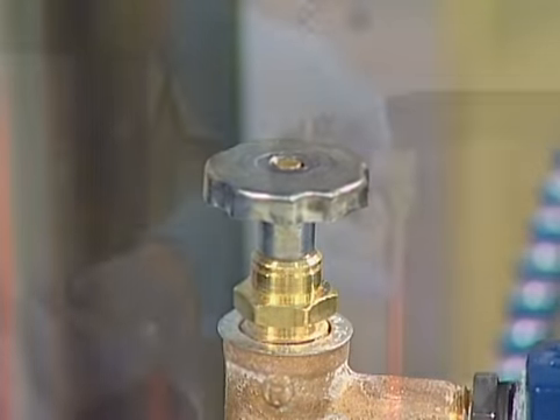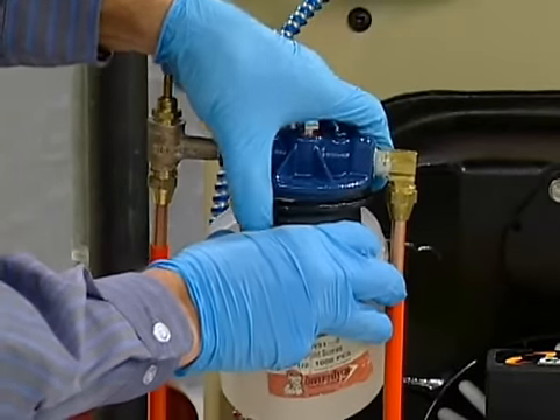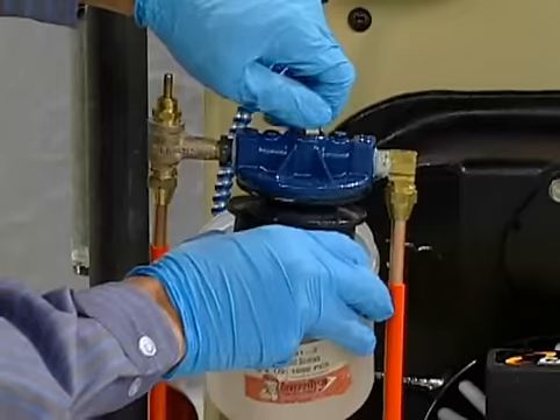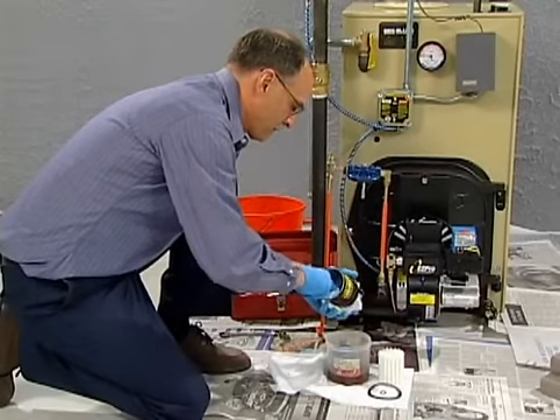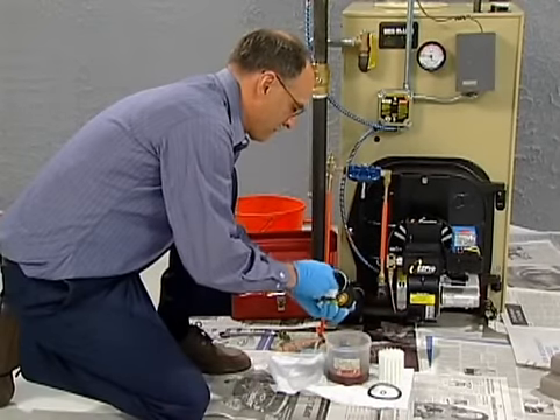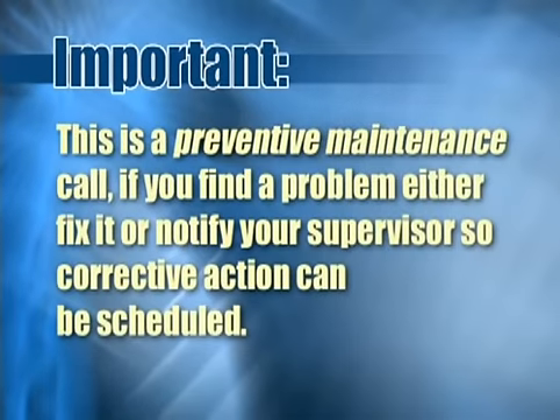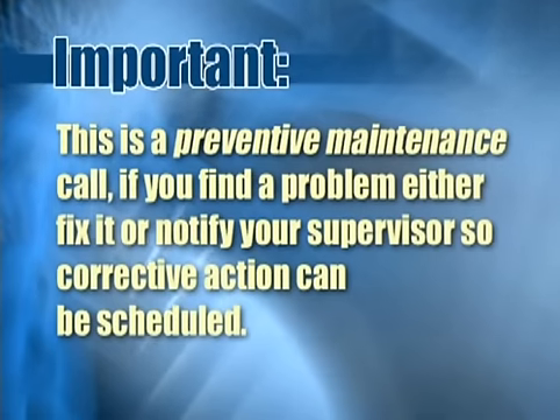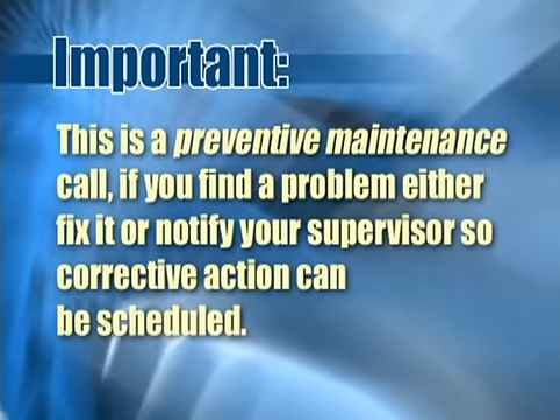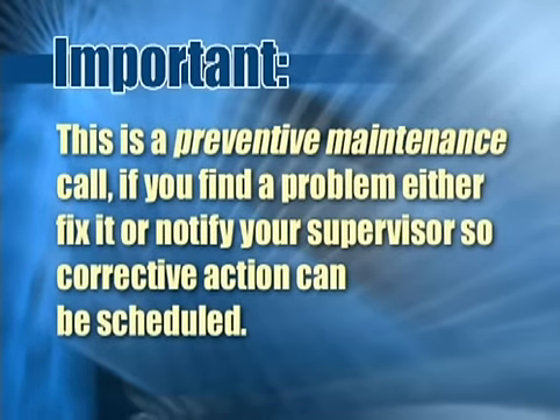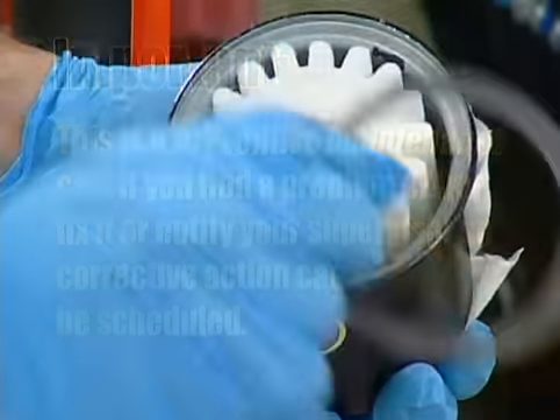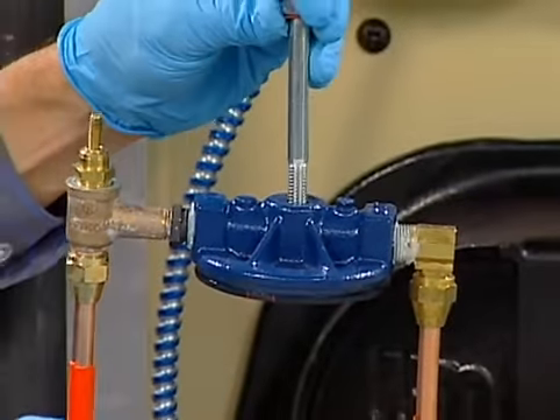Shut off the oil valve and remove the filter canister using a pan to keep any oil from spilling. Inspect the cartridge and filter can for evidence of excessive sludge or water. Remember, this is a preventive maintenance call. If you find a problem, either fix it or notify your supervisor so corrective action can be scheduled. Clean and check the filter can and replace the cartridge and gaskets.